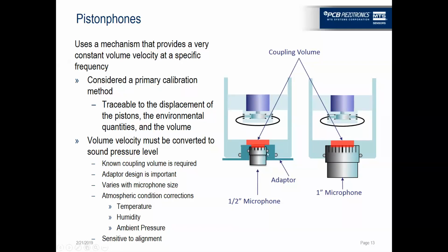Furthermore, because these parts are all being pushed into a cavity, alignment of all these parts is very important. So if you place this on a table and the preamplifier end is tipped down and laying on the table, while the rest of the microphone is suspended and up inside here, this volume is no longer constant, or at least not what it should be with everything pushed in and flat against one another. So doing a calibration with a piston phone can be a bit of a challenge, simply because of all the information that you need to know in order to be able to do the calibration.